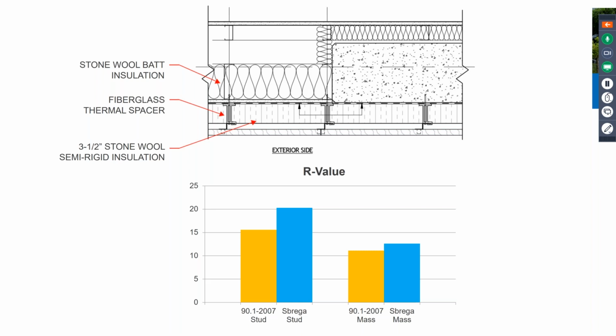So if you look at just the space where all the insulation is, sure, you might meet the code. But if you forget to account for the Z-girts and channels and relieving angles and all those things that go through the insulation, then you're missing the fact that your envelope typically is not in compliance. And so we wanted to at least make sure that we were meeting the code. And you can see in the bottom there's a chart, the stud walls versus mass walls, looking at the baseline effective total assembly R value in yellow versus our actual design in blue. And since this, of course, we've continued to increase the thermal performance of our envelopes.